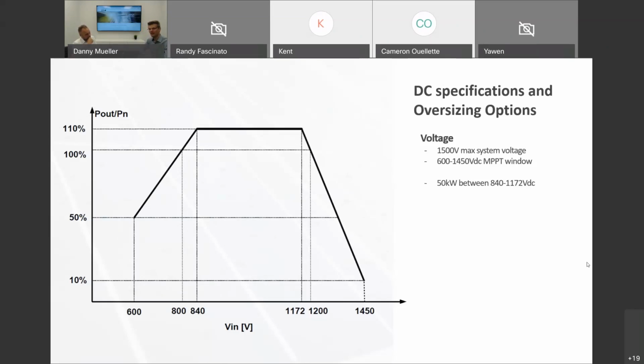So you can, for example, design the first 4 strings with 23 modules and the remaining strings with, let's say, 26 modules per string. Or you can optimize it if you have some partial shading in your system, so that these partially shaded or temporarily shaded strings are connected to one MPP tracker, while the other ones share the other available MPP trackers on that system.